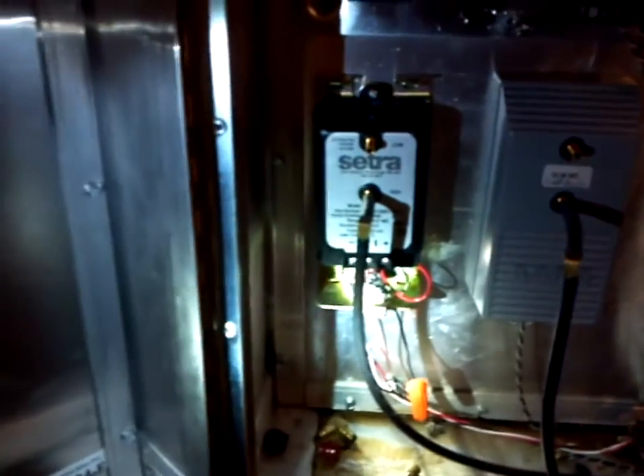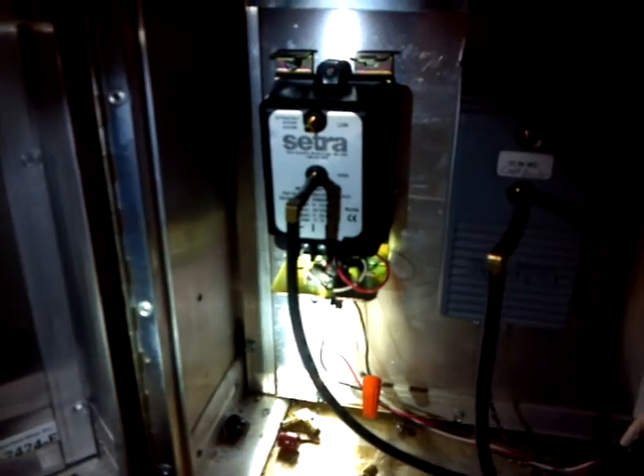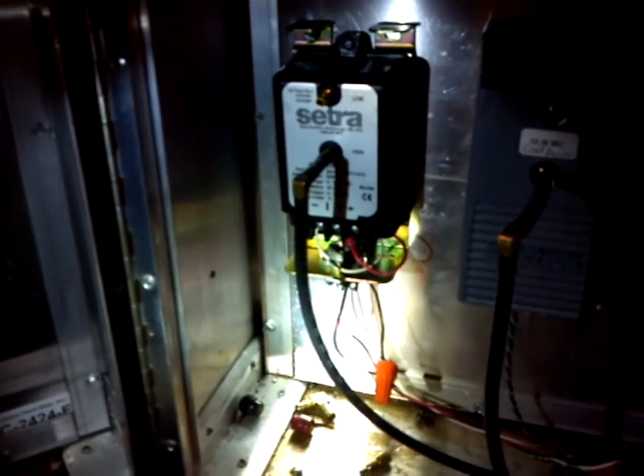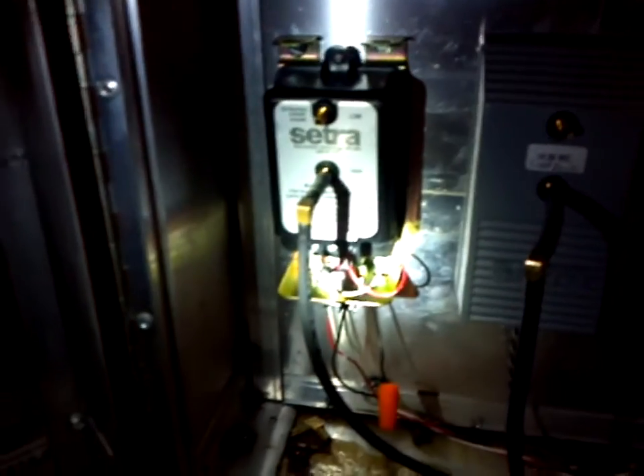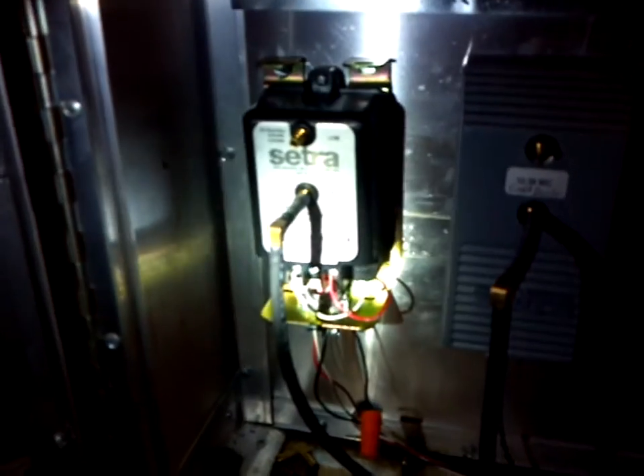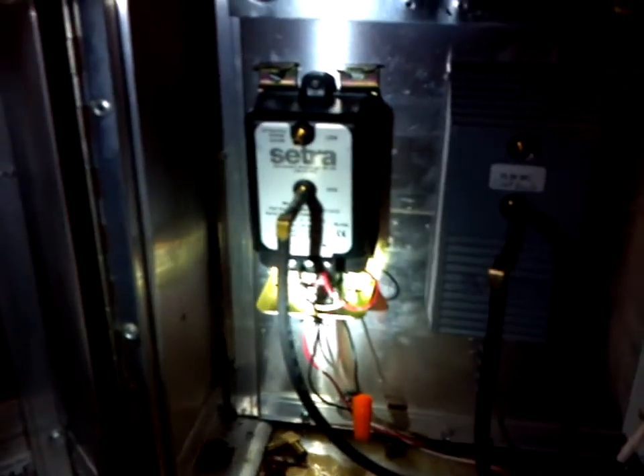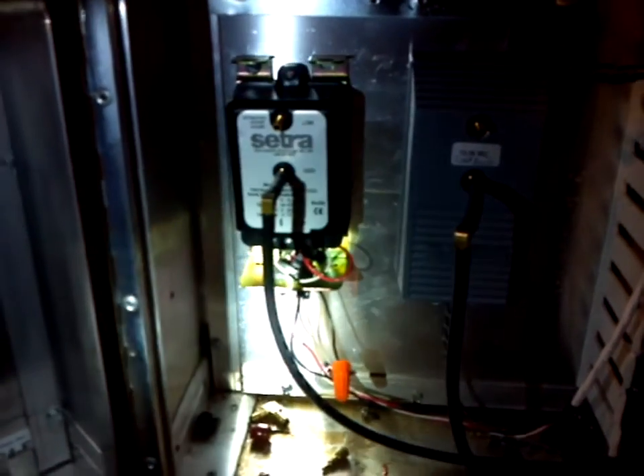To give you a better understanding of how this works, we're going to also talk about some programming in this video to give you a better understanding of some of the steps necessary for setting one of these up to control an air handler. What we've done in this project, as part of a larger project for energy savings, is we have converted a 0 to 5 inch static Setra to a 0 to 10 inch static Setra, which gives us a little wider range in seeing what's going on with the air handler.